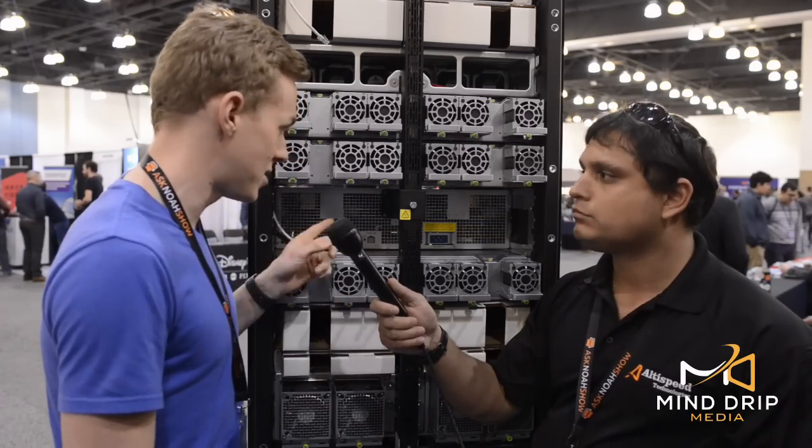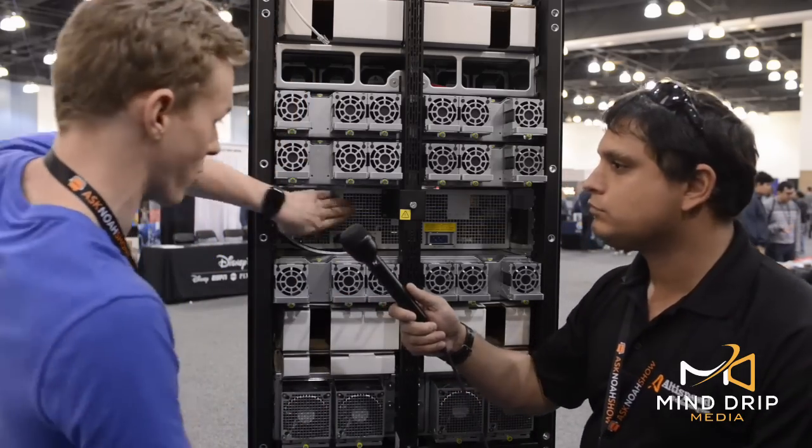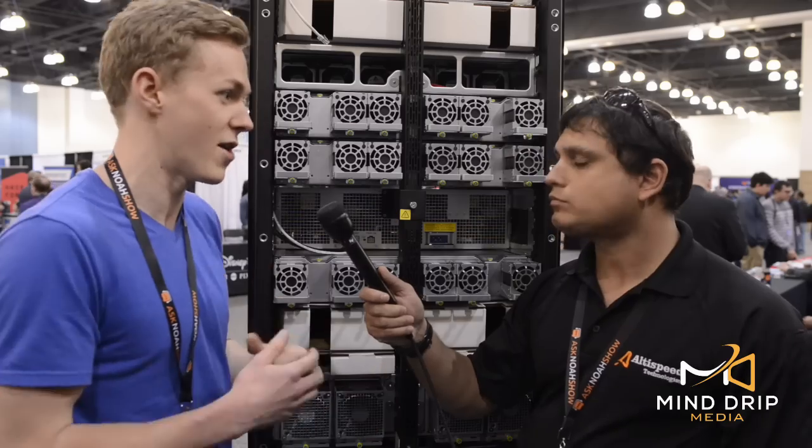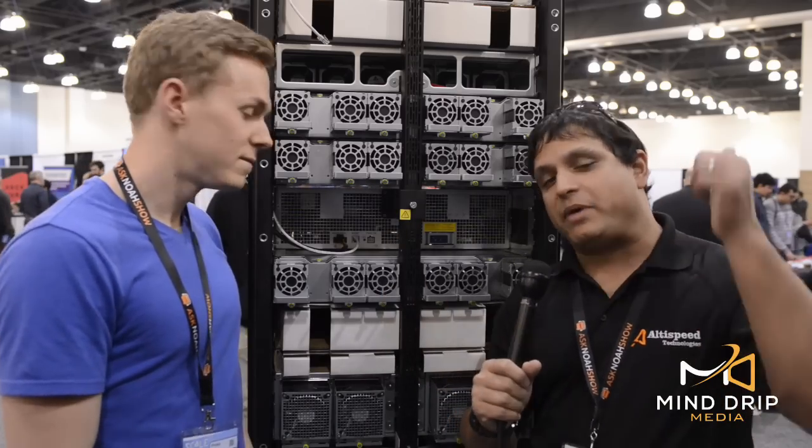And the other nice thing about doing DC in these centralized locations, you'll see there's one up here, and actually one, if I reach down, there's one down here. If you do it in these centralized locations, you can have more efficiency gains by having larger rectifiers, and then your larger battery banks and stuff, and you're not going back to AC again and all sorts of other points of inefficiency. We'll go through as we get back to the front side.